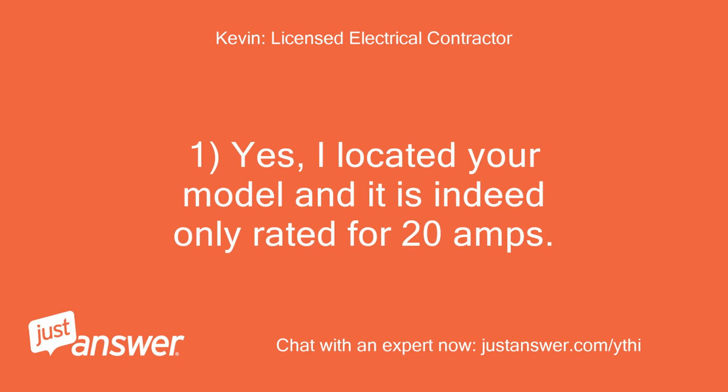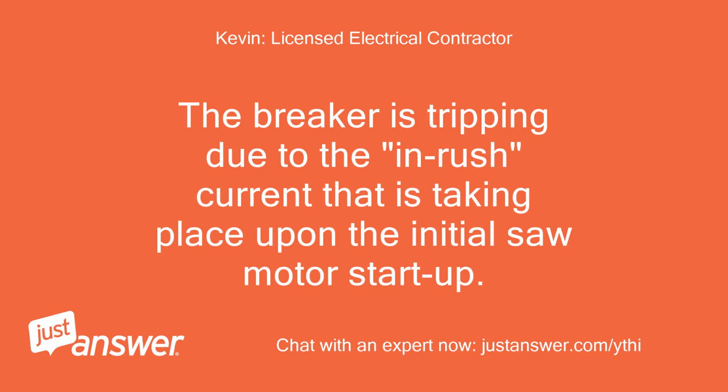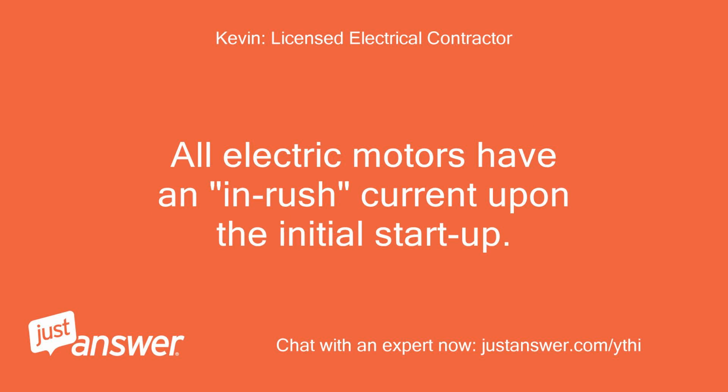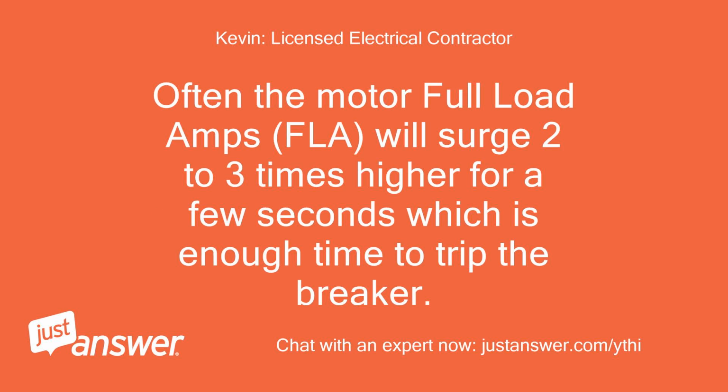1. Yes, I located your model and it is indeed only rated for 20 amps. The breaker is tripping due to the inrush current that is taking place upon the initial saw motor startup. The surge watt rating of this model is not high enough to support the inrush current. All electric motors have an inrush current upon the initial startup. Often the motor full load amps, FLA, will surge 2 to 3 times higher for a few seconds, which is enough time to trip the breaker.